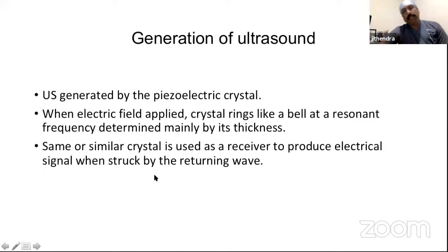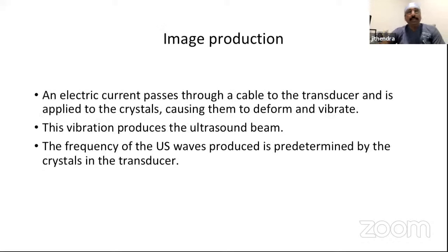Now, how is ultrasound generated? So you know that the probe has piezoelectric crystals. So ultrasound is generated by piezoelectric crystal stimulation. When an electric field is applied, the crystal rings like a bell at a resonant frequency, determined mainly by its thickness. The same or a similar crystal is used as a receiver to produce an electrical signal when struck by the returning wave. So the same piezoelectric crystals in the probe are used for emitting the sound waves as well as receiving them. And how is the image produced?